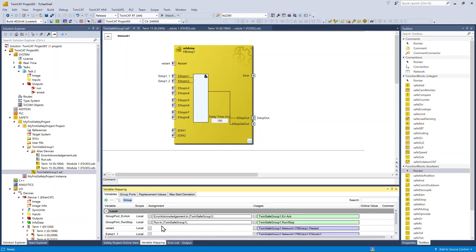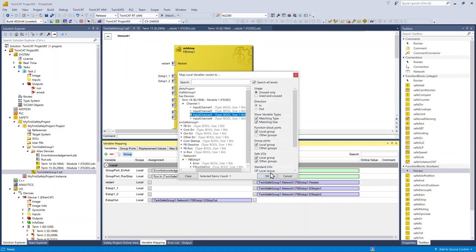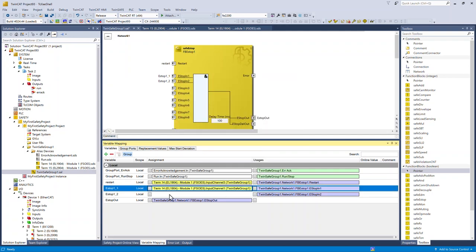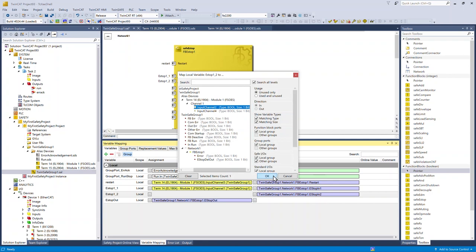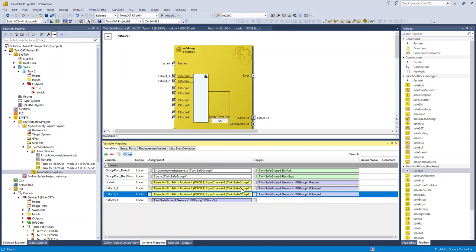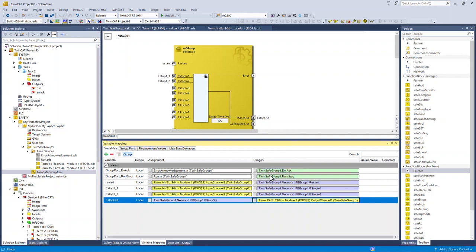Now I'm going to map those variables to physical locations on the hardware. The restart is going to be input three on the EL1904. And the e-stop is connected to channel one and channel two of the EL1904. The e-stop output is going to be connected to channel one of the EL2904.